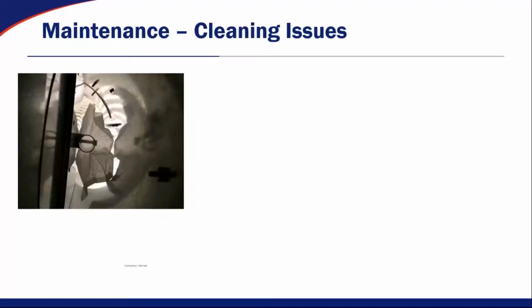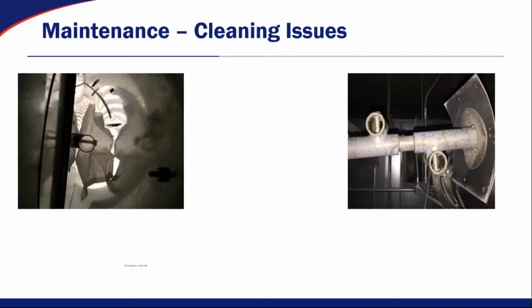Now, when you look at different technologies, it's not just a flow cross or an orifice ring that can get clogged up. Vortex shedding is another product with a different approach to measuring airflow than a traditional flow cross. However, you have an obstruction in the middle of the ductwork that can still catch debris. In this particular picture, there's a tissue stuck on that sensor, which does happen in fume hood environments. People take Kim wipes and tissues and throw them through the ductwork, and they're going to get stuck on anything that's sticking out in the middle of the ductwork.